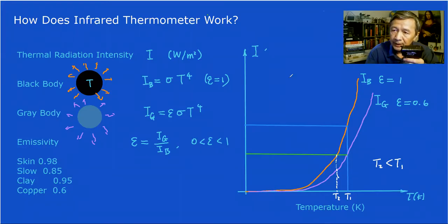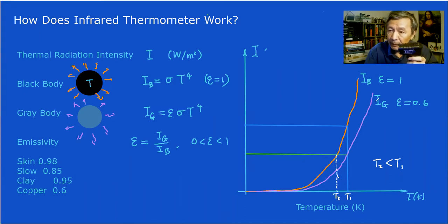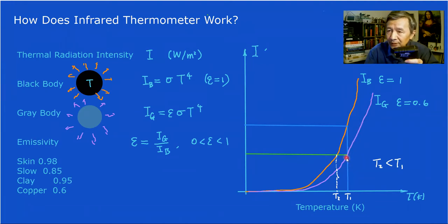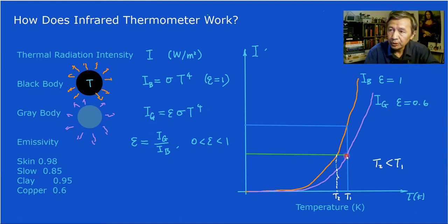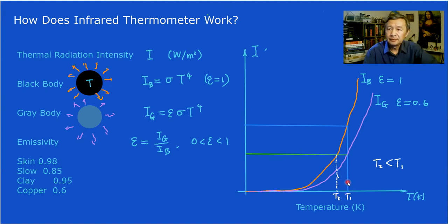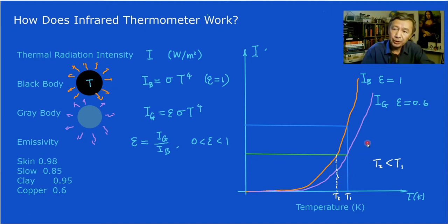By adjusting the emissivity on this IR thermometer, the machine will use the purple diagram — the gray body curve — to determine the temperature. In this way, the temperature displayed will be identical to the actual temperature of the gray body object being measured.